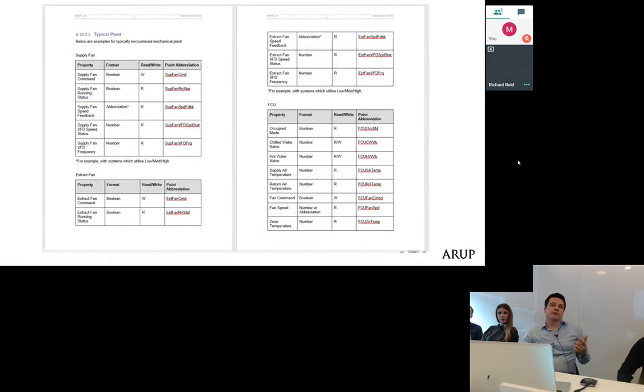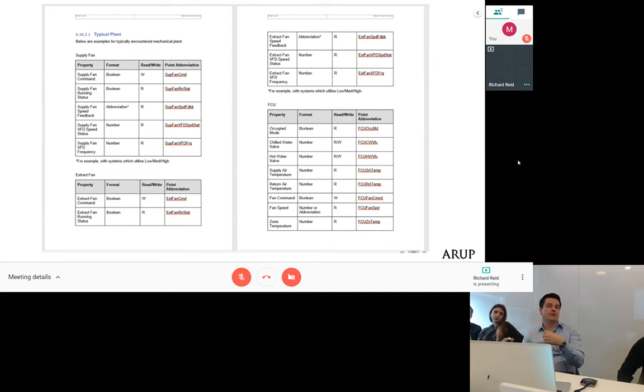The second critical point is that not only do we need the device name and abbreviation that's always the same, but when you design and implement the building, these are all the points that need to be made available. Some are read-only, others need write-back capability, i.e. I want to change the temperature in this meeting room, turn the air conditioning on and off, or turn the lights on and off. By defining that in our design guidelines, we ensure that when it gets specified and implemented, the information will be available for any possible use cases British Land are looking to implement.